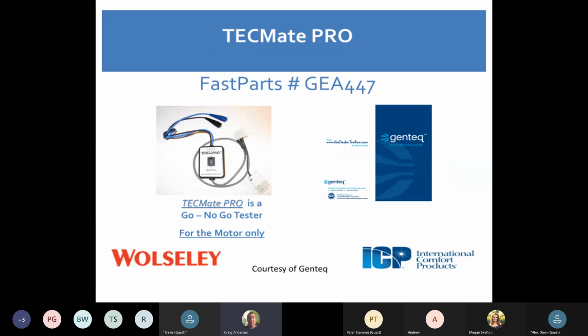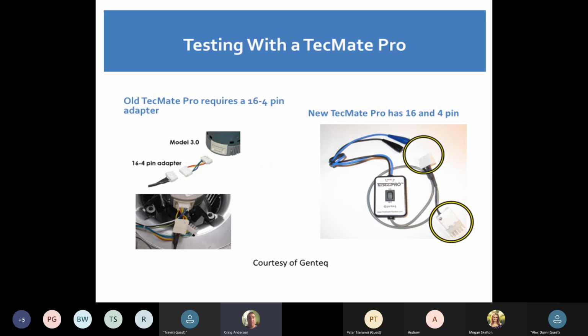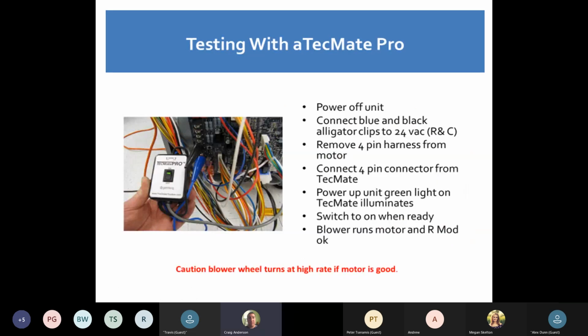So this is the TecMate Pro ECM motor tester, made by Genteq. The old style Testmate Pros never had the little 16 to 4 pin adapter. At that time, they didn't have motors that had different plugins. The new testers come with all the adapters built in, the 16 and 4 pin right on the tester. Very easy to operate. Everything is hooked up to this tester. There's nothing to add on to it. As soon as you take it out of the box, it's ready to plug into your motor and plug into your gas furnace.